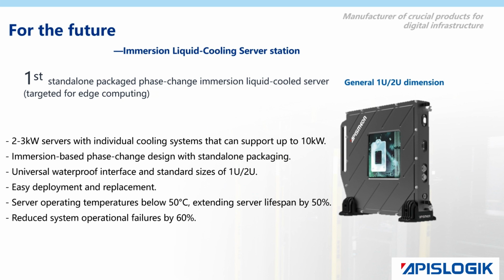The world's first universal standalone packaged phase-change immersion liquid-cooled server. It is designed for 2 to 3 kilowatts power range, available in 1U and 2U sizes, and operates without fans. With its phase-change immersion cooling technology, it offers easier deployment and replacement, extending the lifespan of IT equipment by 50% and reducing system failures by over 60%.